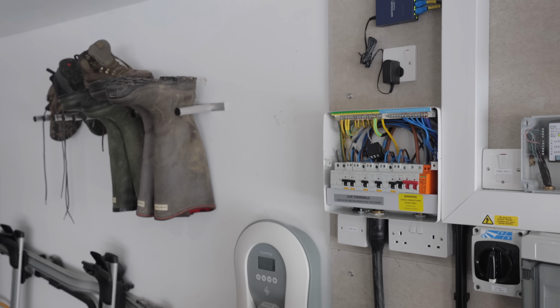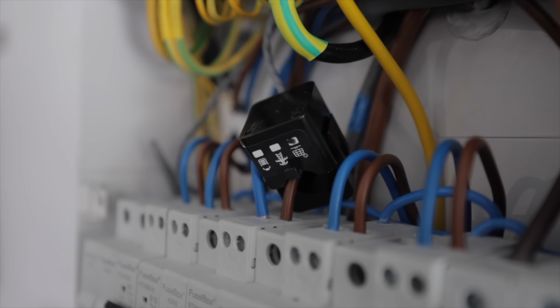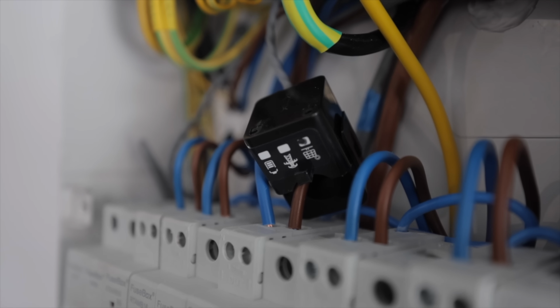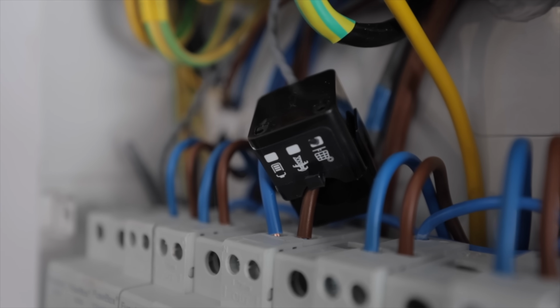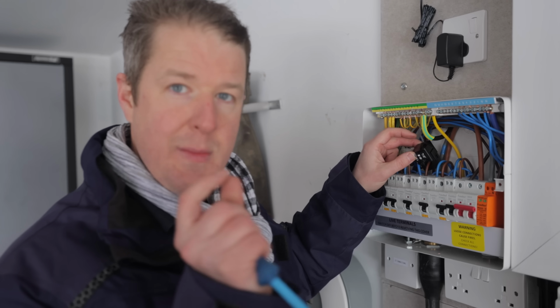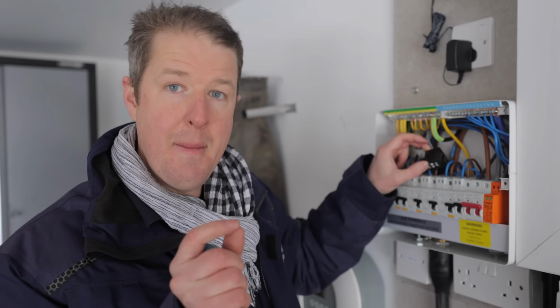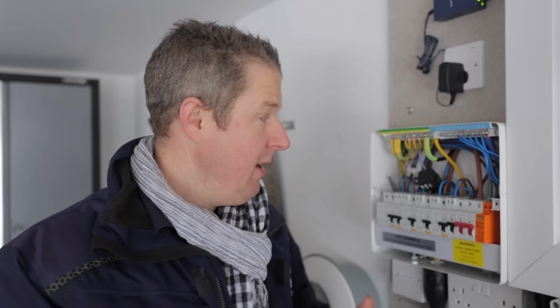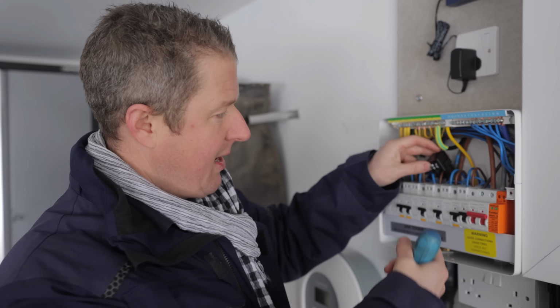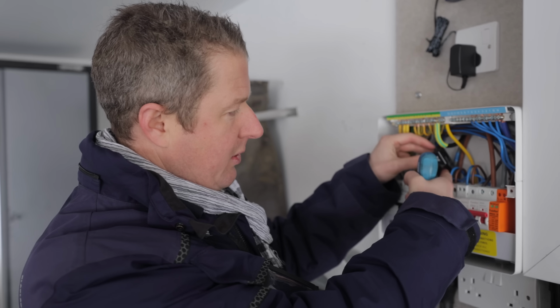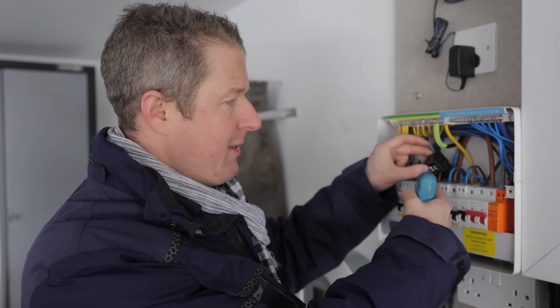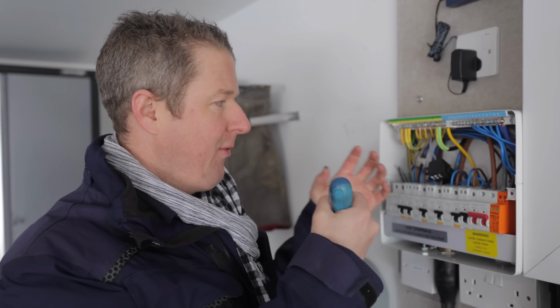Now, how do they work, I hear you ask? Well, it's exactly what it says on the tin—it's a current transformer. Essentially it transforms the current flowing through this magnetic coil into a small, minuscule amount of voltage, actually read in millivolts. It's like a miniature transformer, converting the magnetic field of the cable passing through it into a small amount of voltage.